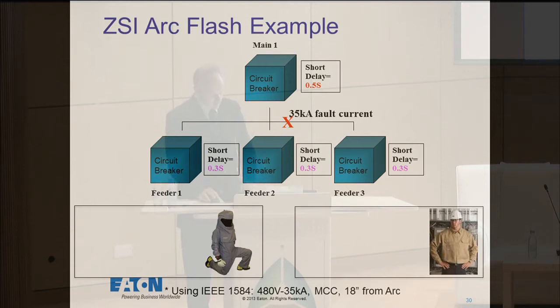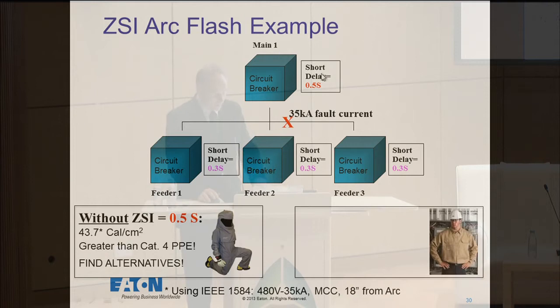So for that fault, what happens here is without zone selective interlocking, this breaker is going to wait a half a second. At a half a second, it comes up to 43 calories. And when you start looking at the tables in the IEEE standards and in the NFPA 70E for electrical safety of personnel, you start saying that number is way too high to protect it. So you may have seen some of these in the industrials. They have these suits that they put on. Some people call them a moon suit. They put a big thing over their head. It's flame retardant clothing that's very heavy, to protect the workers' clothing from catching on fire. One of the problems is the heat, especially in an environment such as yours; when you put this on, the worker's subjected to a lot more heat just from the body heat. So this is a tremendous amount of energy that someone would have to suit up in something like this in order not to get thermally burned.